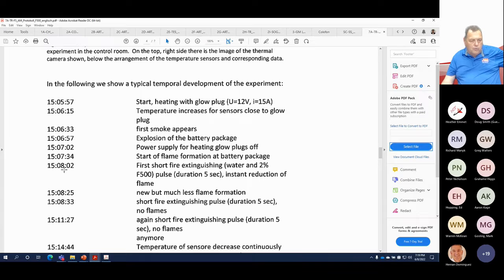At 802, we do the first shot of the F500 agent - water with 2% solution, a 5-second burst, just 5 seconds. From 802 to 807 we get an instant reduction of the flame and a big reduction of the heat. Then we wait - we don't do the second burst for another 30 seconds. Between 807 and 825, about 20 seconds, we get a little more flame, but much less flame formation.